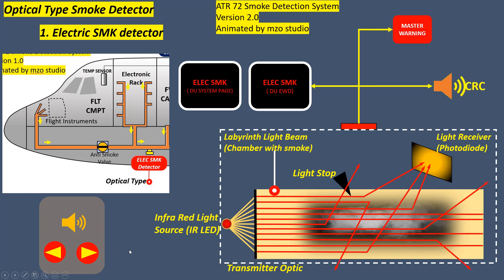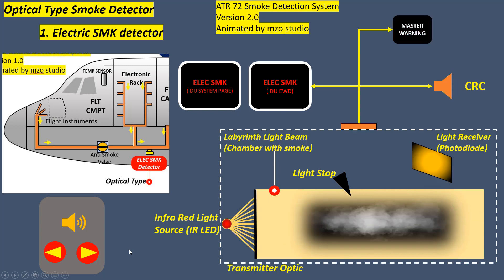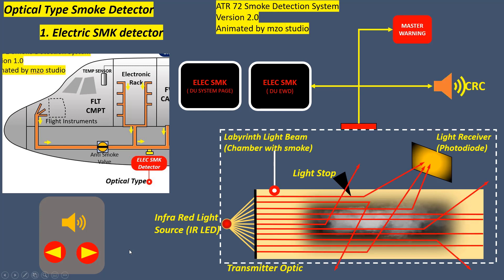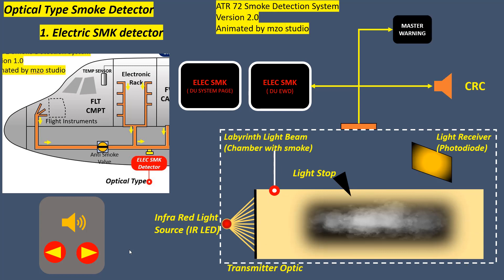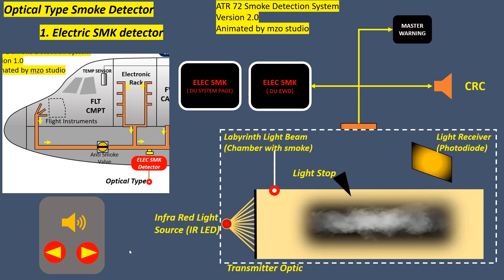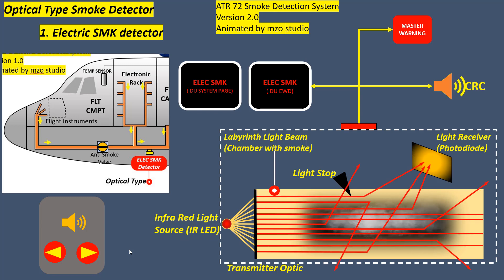When smoke particles are present in the optical path, the light source is deflected to the photo diode. The electrical signal is processed by the electronics. When the preset threshold is reached, the circuit generates a warning signal.